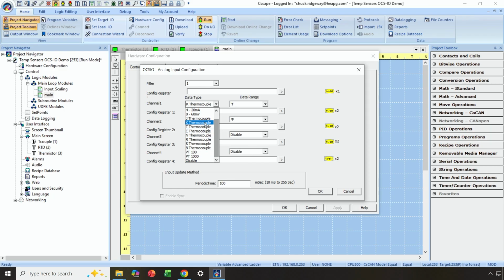But in this demonstration, I'm using a Type K thermocouple, and I want to use degrees Fahrenheit as my temperature reading in this case. The values for this module, when we're talking about temperature sensors, are reported in 10th degree increments. So if I have a 20.0 degree reading, I'll have a value of 200. That'll be reported in the input register, if you will. Okay, on the second channel, I've got a PT100 selected because I've got a Platinum 100 RTD. Again, I'm going with degrees Fahrenheit. And then I went ahead and disabled the unused channels.